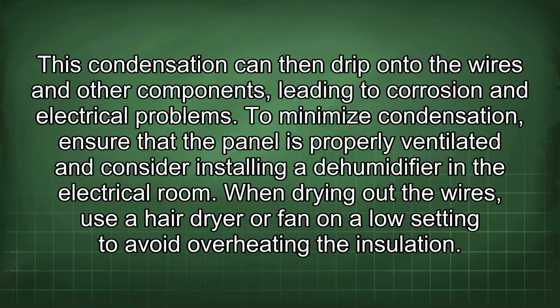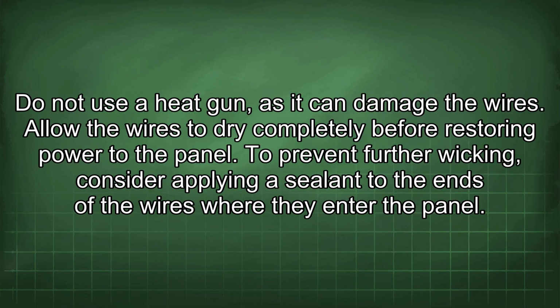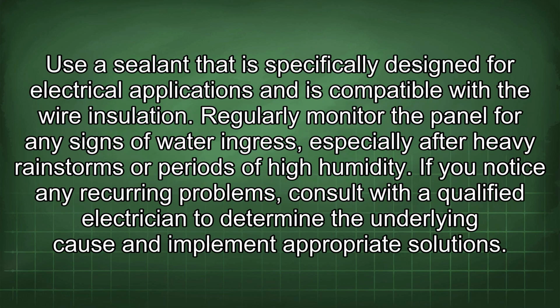When drying out the wires, use a hairdryer or fan on a low setting to avoid overheating the insulation. Do not use a heat gun, as it can damage the wires. Allow the wires to dry completely before restoring power to the panel. To prevent further wicking, consider applying a sealant to the ends of the wires where they enter the panel. Use a sealant that is specifically designed for electrical applications and is compatible with the wire insulation.